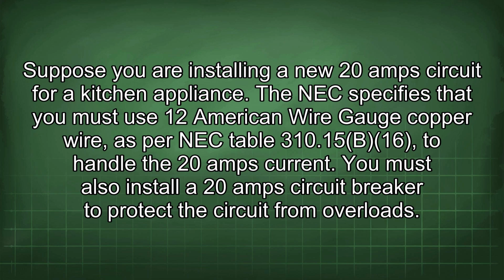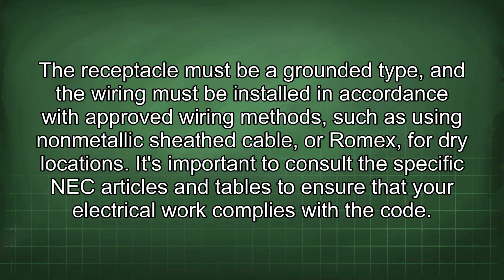You must also install a 20 amp circuit breaker to protect the circuit from overloads. The receptacle must be a grounded type, and the wiring must be installed in accordance with approved wiring methods, such as using non-metallic sheath cable or Romex for dry locations. It's important to consult the specific NEC articles and tables to ensure that your electrical work complies with the code.